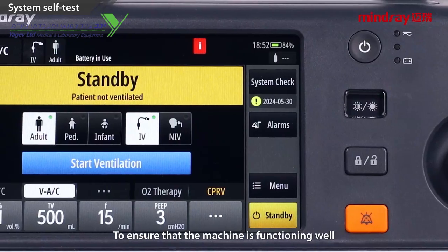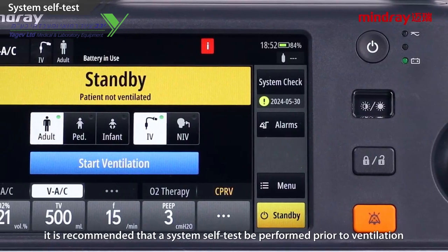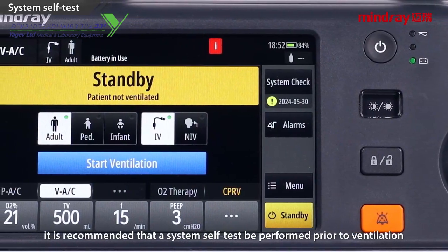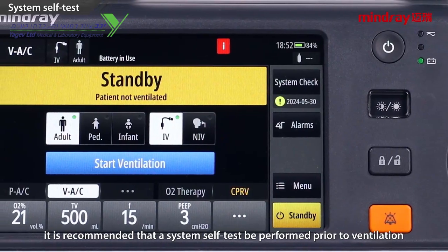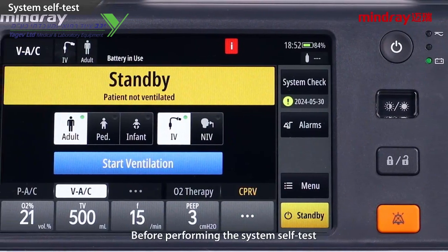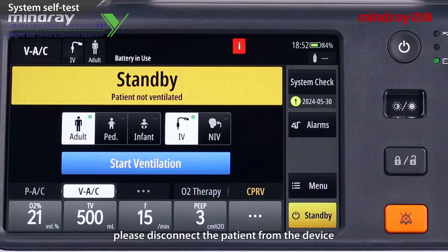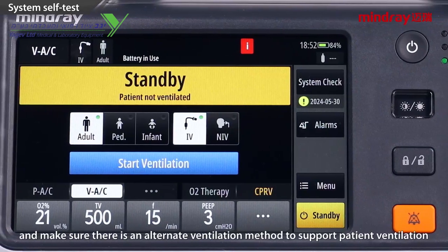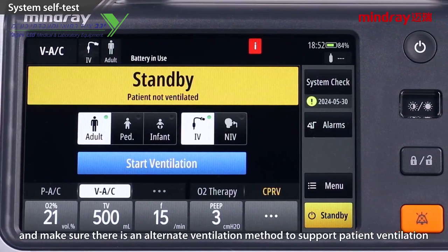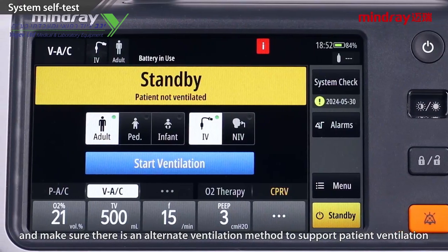To ensure that the machine is functioning well, it is recommended that a system self-test be performed prior to ventilation. Before performing the system self-test, please disconnect the patient from the device and make sure there is an alternate ventilation method to support patient ventilation.